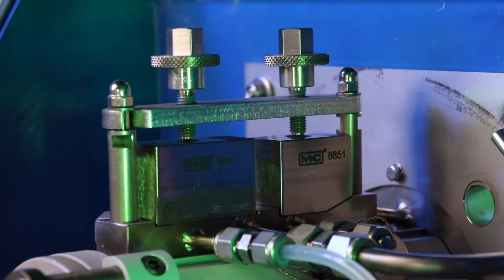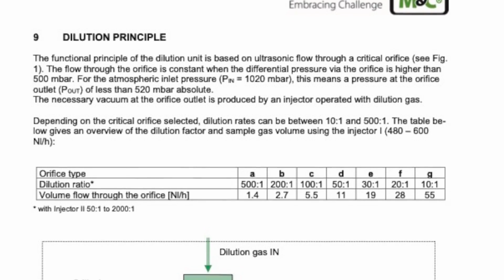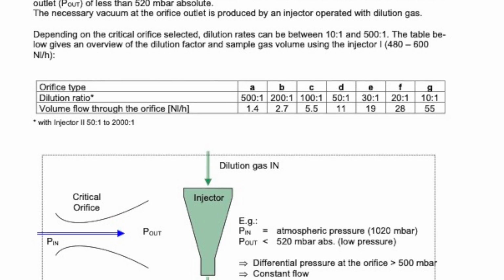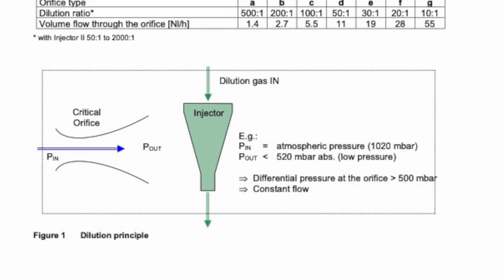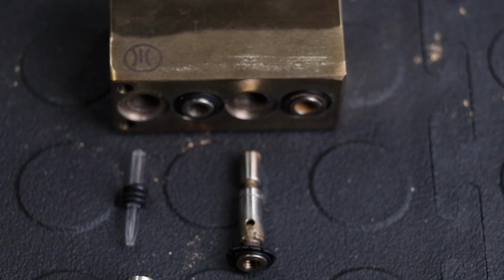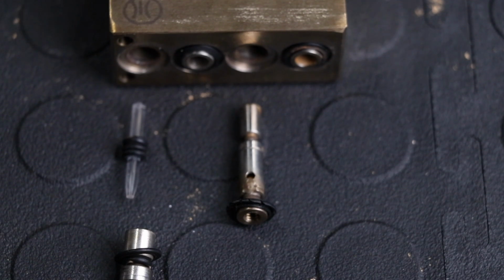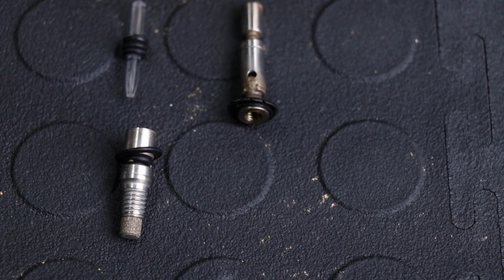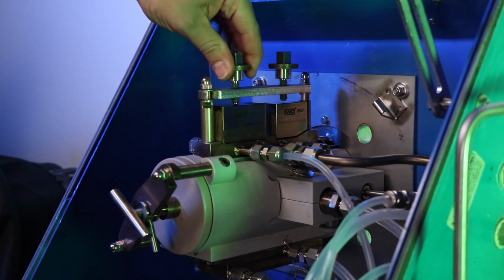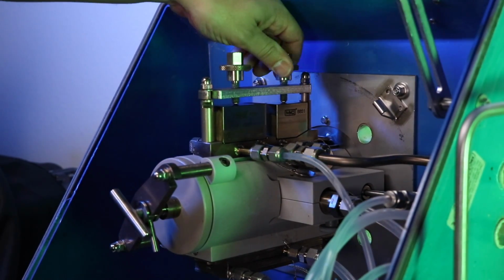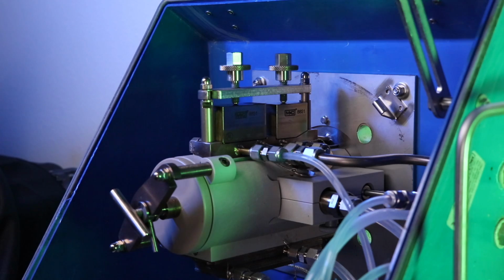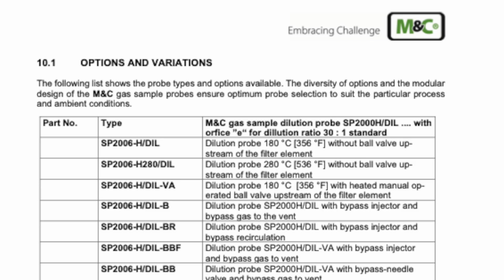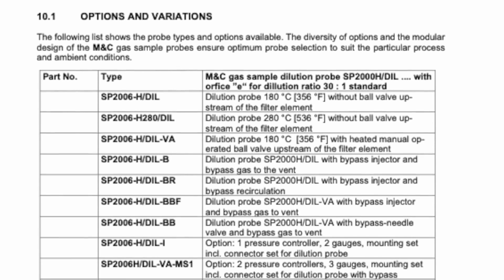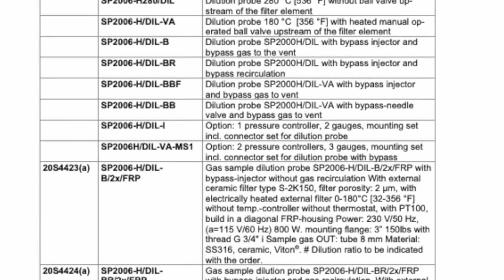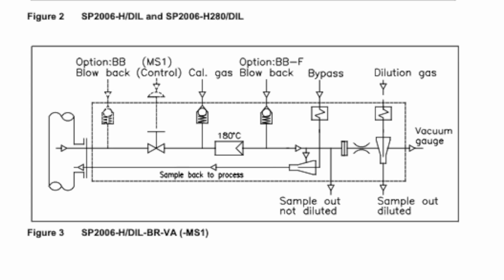The SP2006 dilution unit is based on an sonic flow through a critical orifice. See Figure 1 in the user manual for a full explanation of the dilution principle with associated drawings. One of the most important features of the SP2006 is the position of the dilution block. The dilution and eductor blocks, including the critical orifice, are mounted directly to the probe body and therefore heated up with the probe. The modular design of the SP2006 allows for configurations to support many process and ambient conditions.